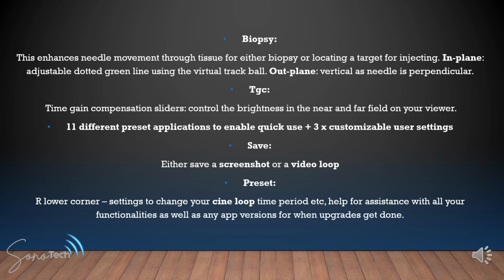You've got two options, an in-plane or an out-plane mode. The in-plane is where you're coming from an angle and coming to either biopsy or inject into an area. You get a dotted green line on your viewing device, which you can then track. The out-plane mode is when you're coming in vertically, as your needle is then perpendicular. You have a line on your probe that will correlate exactly with that line going down. You'll see a bit later in the videos, it'll also have a round circle that you can then move around to ensure you know exactly where you're wanting to inject.